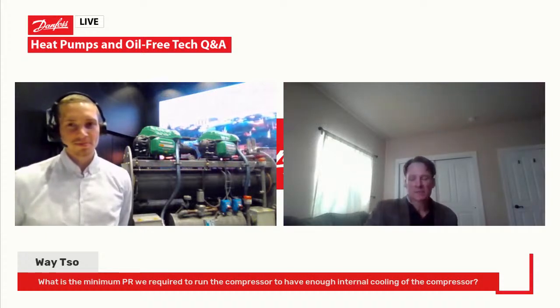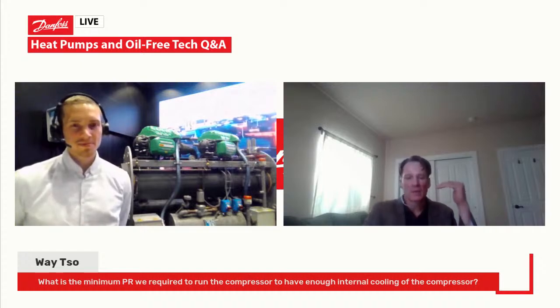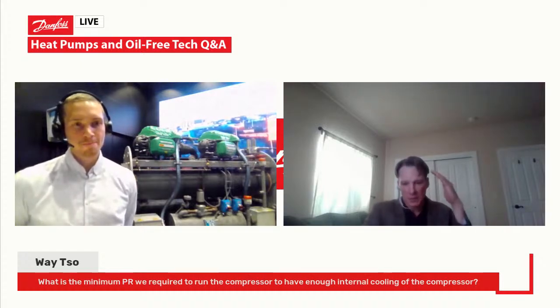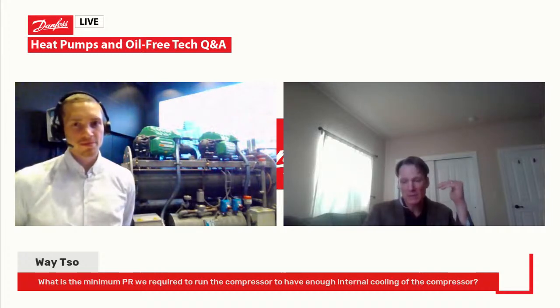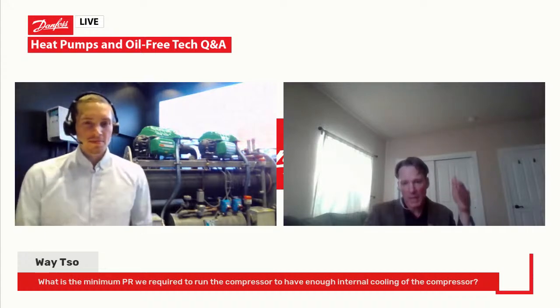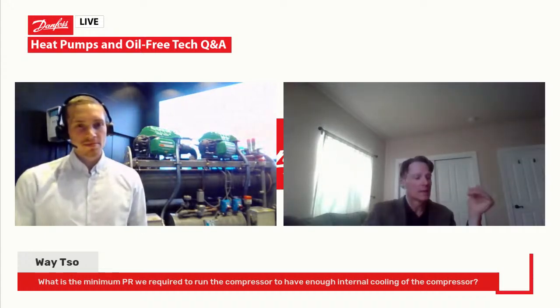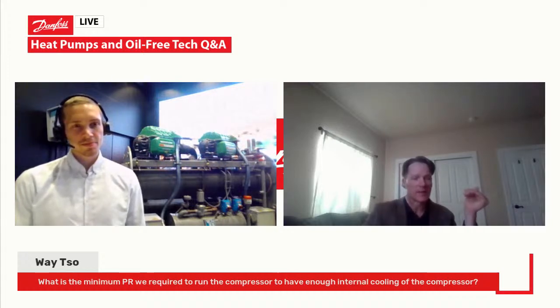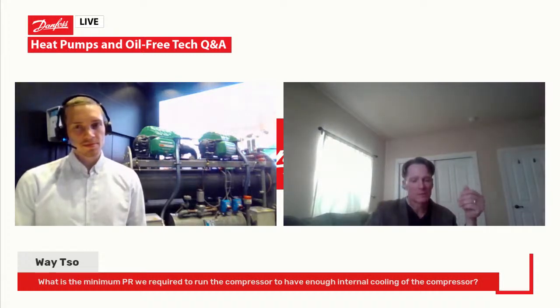one of the primary applications of Turbocore technology from a chiller standpoint is in data center applications. And data center applications have had the phenomenon over the last 25 years of increasing the cooling temperatures significantly, on average 25 K. When I first started in this industry, they were cooling at about 7 degrees Celsius, which is comfort cooling temperatures, which was designed for combined sensible and latent loads. If you're cooling only a sensible load, and specifically CPUs in a data center, you don't need to do that.